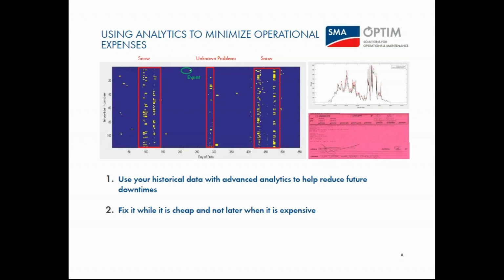With these advanced insights, we can recommend a course of action that might preempt a larger repair issue. Things like inverter filters and fans, if you're noticing some additional strain on those, can be addressed preliminarily by looking at the data points and fixing those, changing filters or fixing the fans before a more expensive inverter failure happens.